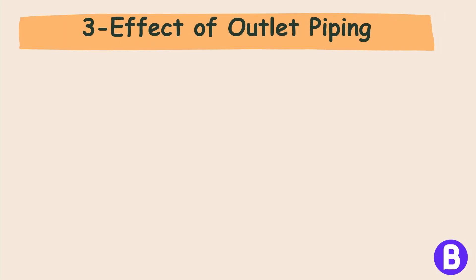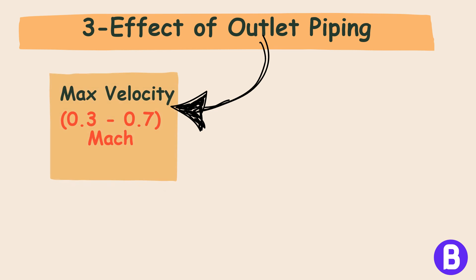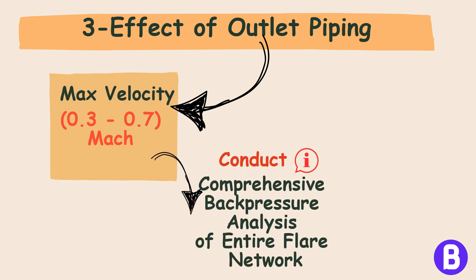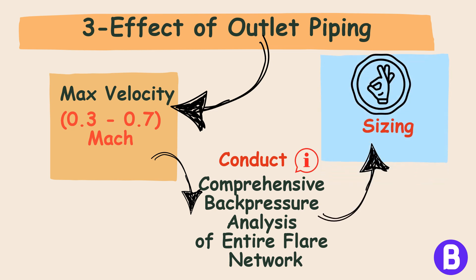Therefore, the outlet piping should have a maximum velocity ranging from 0.3 to 0.7 Mach, and a comprehensive backpressure analysis of the entire flare network must be conducted to ensure that the outlet piping is appropriately sized.